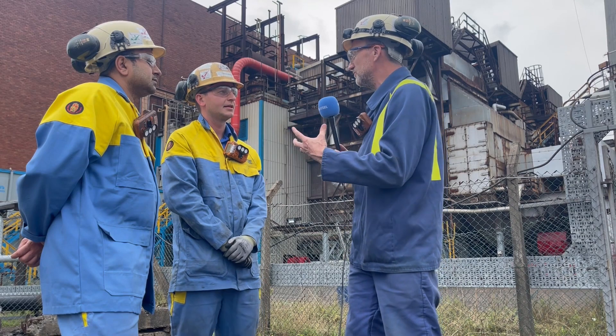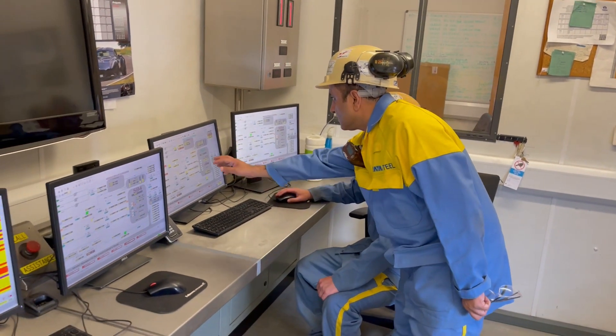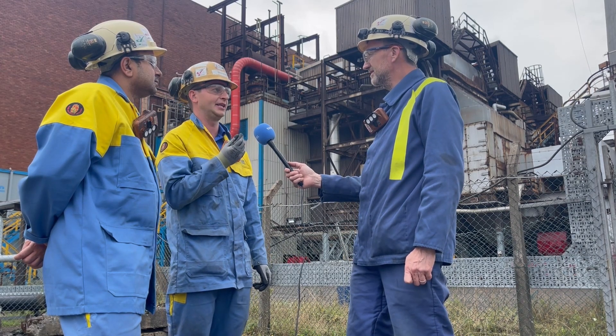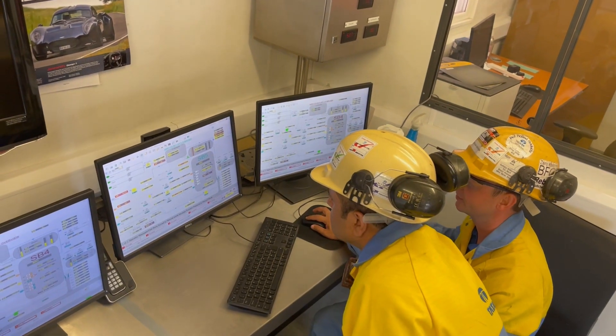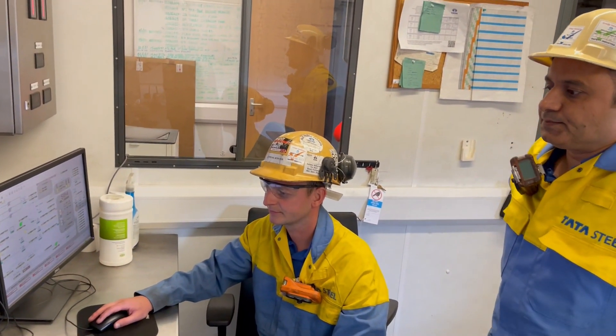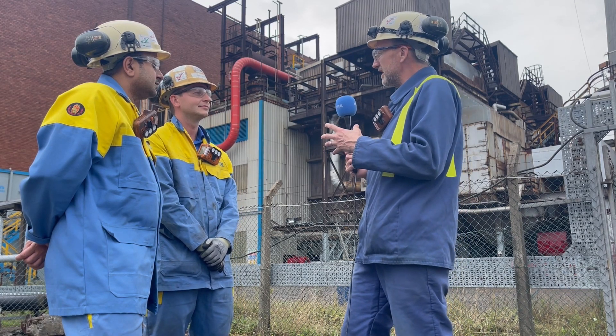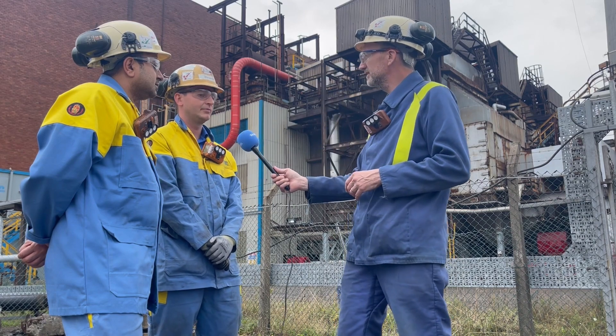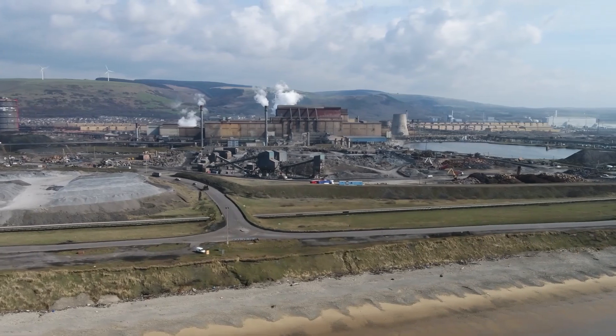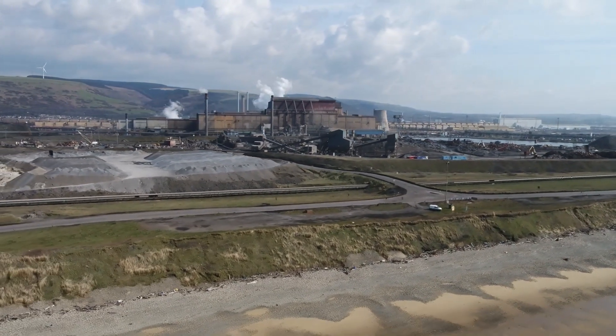So what's been the answer — what's the project you two have been working on? We've just implemented a new £380,000 project. What it does is use CV analyser technology: we measure the calorific value of the blast furnace gas and only inject the perfect quantity of natural gas when that calorific value is low. So instead of using a very large amount of natural gas constantly, it's a very small amount injected infrequently — and that's reduced overall natural gas use by 80%. This project will reduce our overall CO2 emissions by 10,000 tons per year, which is equivalent to the emissions from flying an airplane around the world 888 times — so we're talking a very significant amount of carbon.